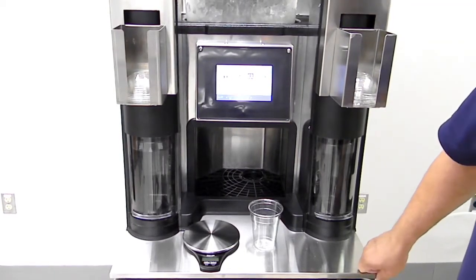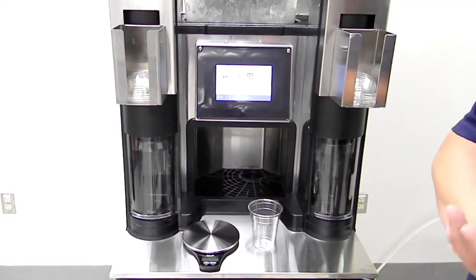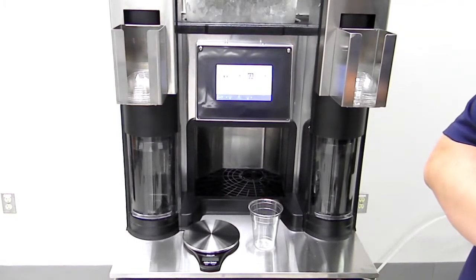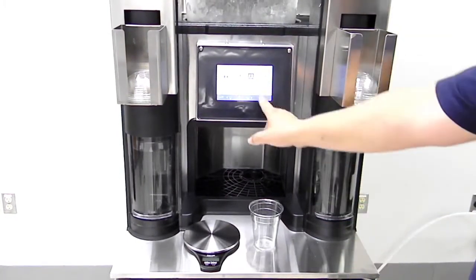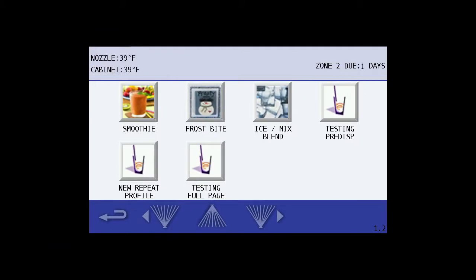In addition to that, we want to make sure that Zone 2 cleaning has been completed more than 1 hour prior. On the screen, you can get a reference to your Zone 2 cleaning right on the front screen, upper right corner. It'll tell you how many days you have left on the 7-day timer. In this case, you can see we've still got 1 day left, so it's been at least 6 days since this unit went through Zone 2 cleaning.